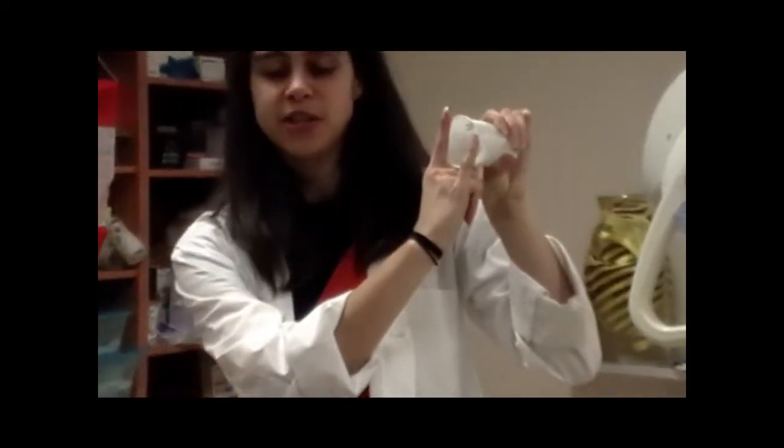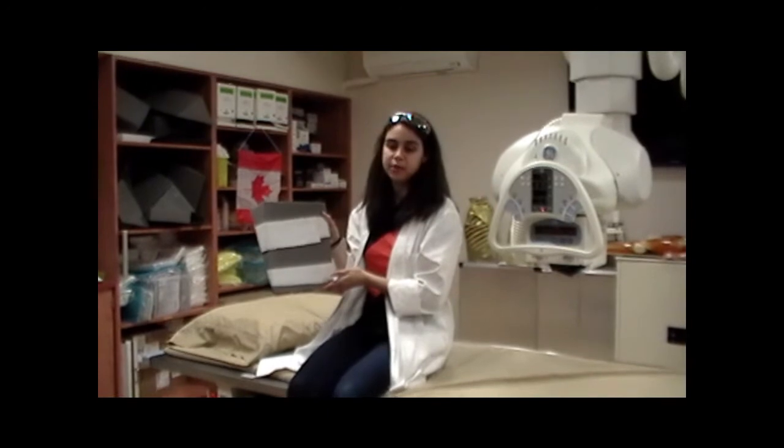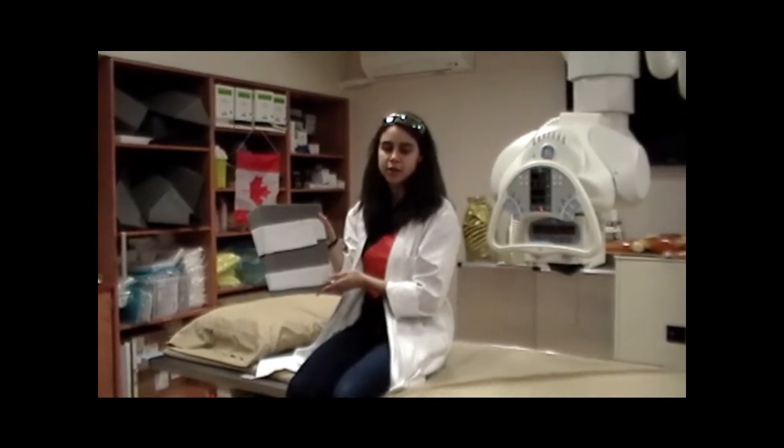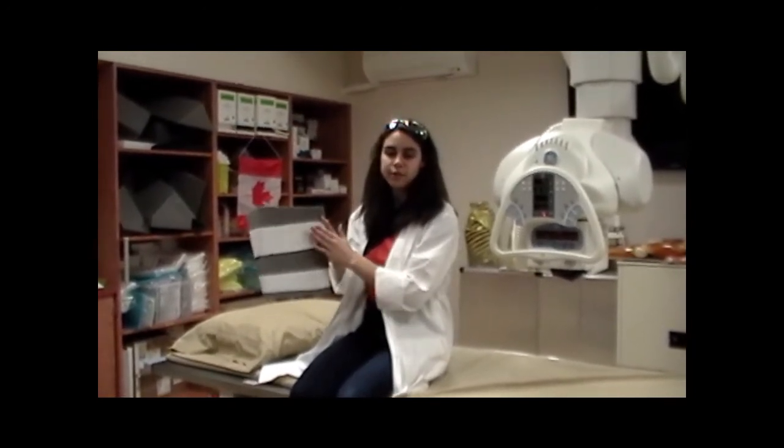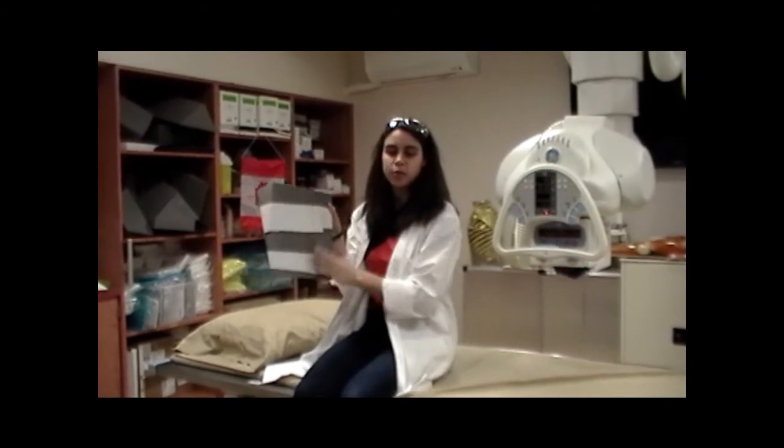Most X-ray machines in the hospitals are dual focus, meaning they have 2 filaments in the focusing cup, one large and one small, which correspond to a large and small focal spot on the anode. Only one of these is energized at a time. Depending on the filament used, there are 2 different focal spot tracks on the anode. Each have a different angle to help aim the X-rays down towards the patient.